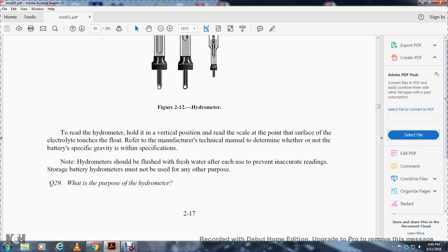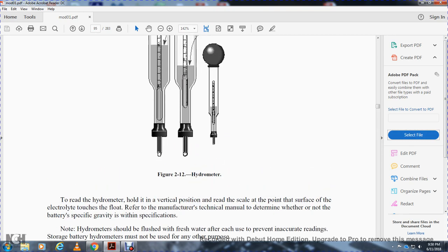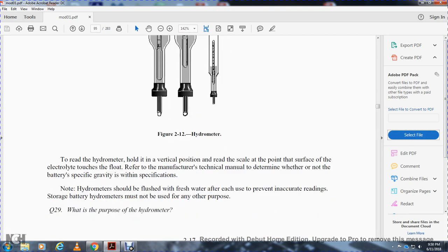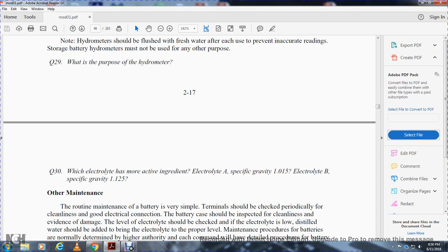To read the hydrometer, hold it in a vertical position and read the scale at the point where the surface of the electrolyte touches the float. Refer to the manufacturer's technical manual to determine whether the battery's specific gravity is within acceptable limits. The hydrometer should be flushed with fresh water after each use to prevent inaccurate readings. Storage battery hydrometers must not be used for any other purpose.